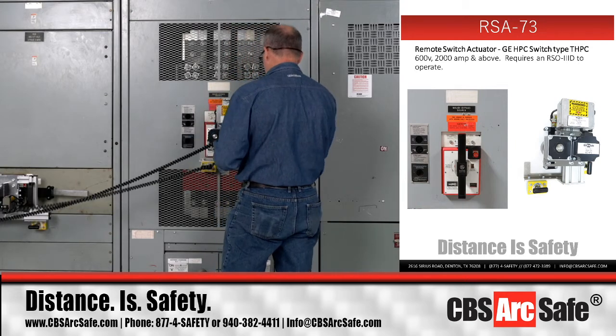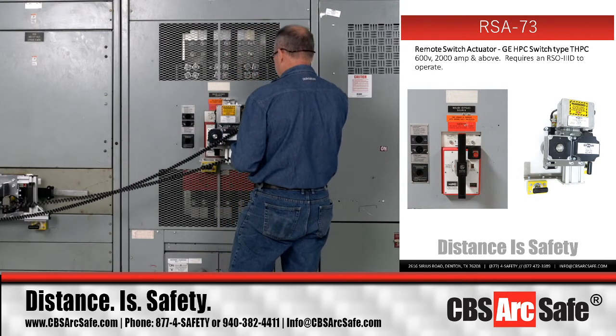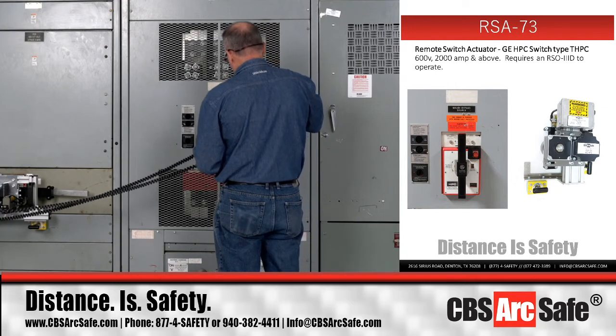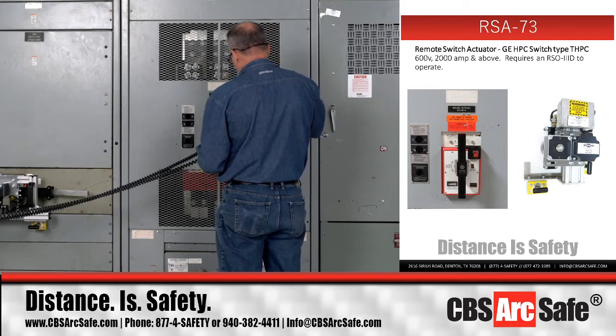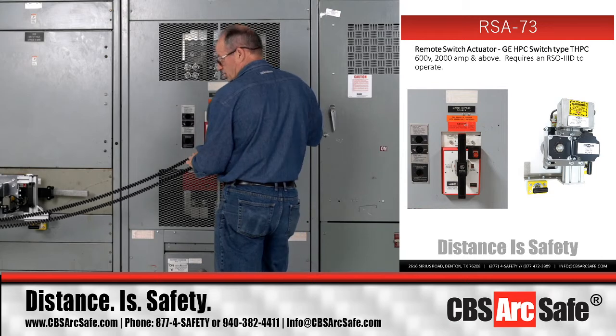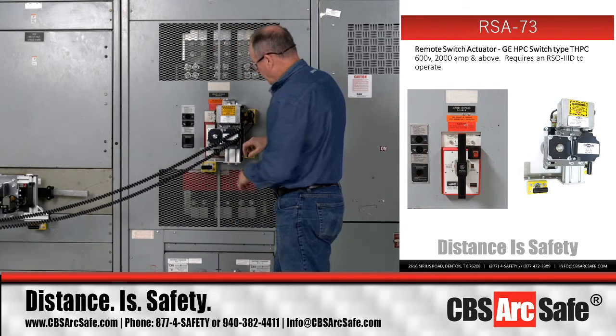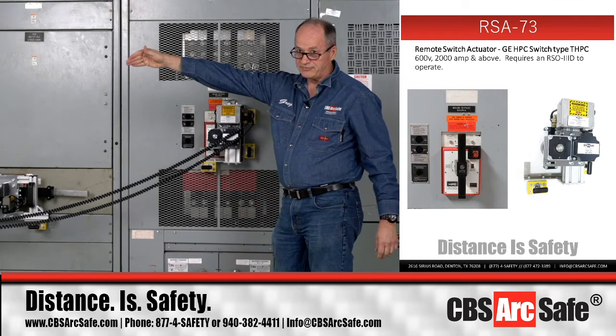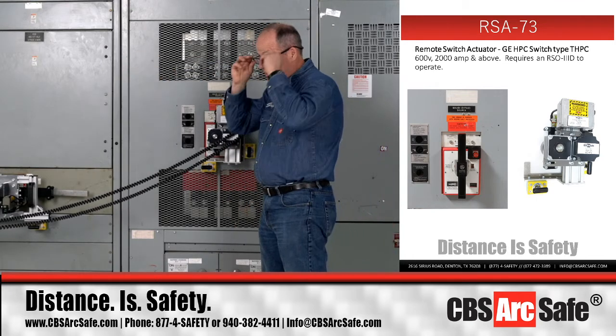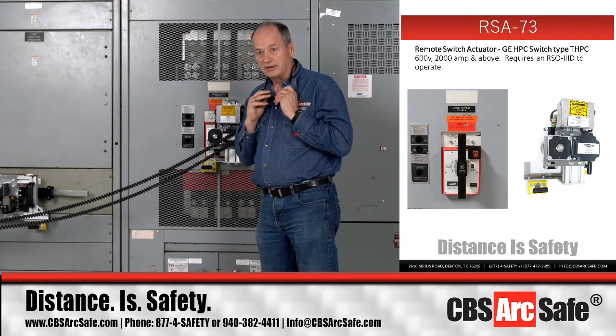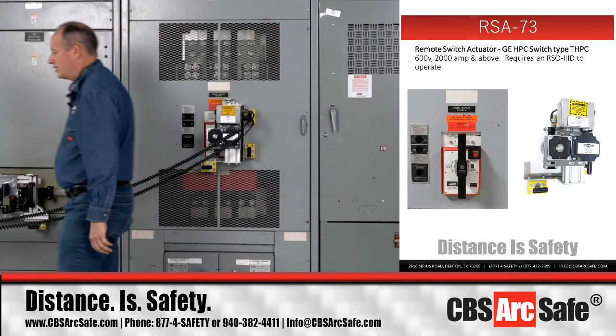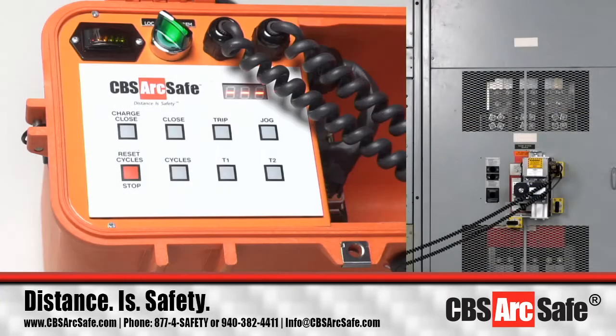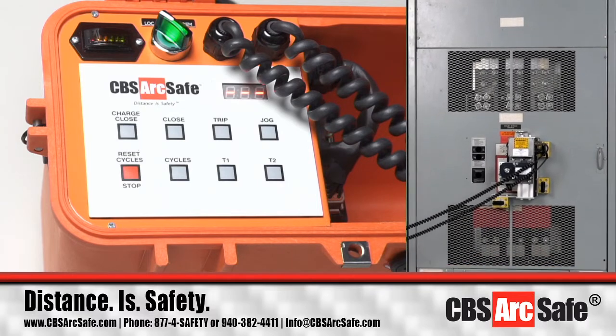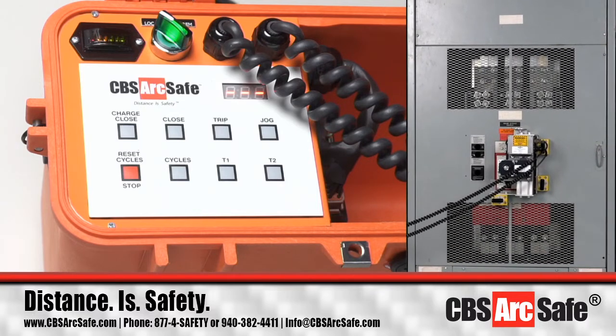The length of the cable is about 30 to 35 feet when stretched out, roughly about 10 meters. The funny thing is, looking at it right now, you'd think there's a lot of tension in that cable. Well, when you stretch this thing out, it will go out that far. So there's no need to be right in front of the switchgear. I know the common human tendency is that somebody's been doing this for 20 years and they want to be able to stand there and watch things happen. Well, the whole purpose is to be outside of the arc flash hazard boundary.